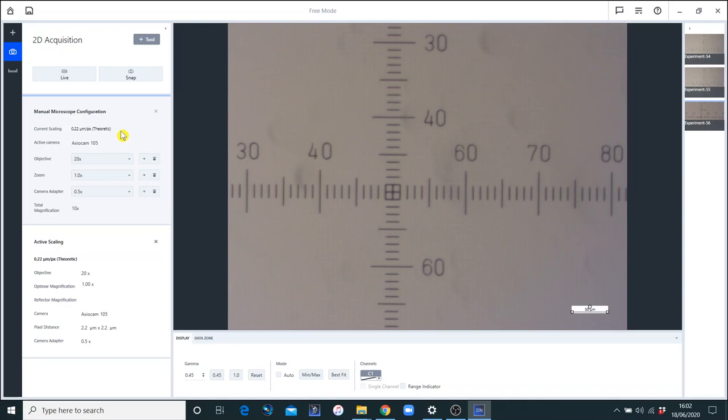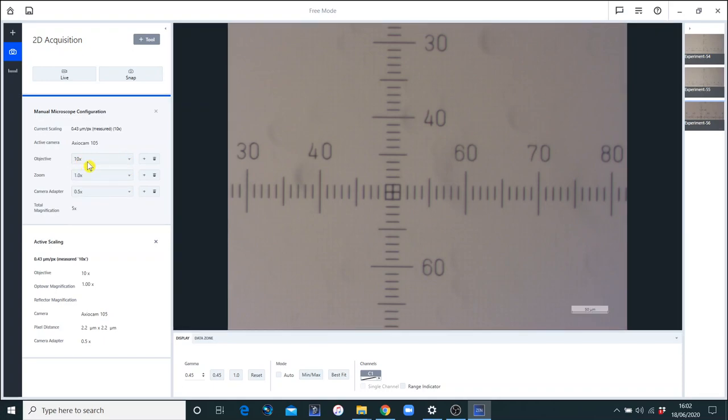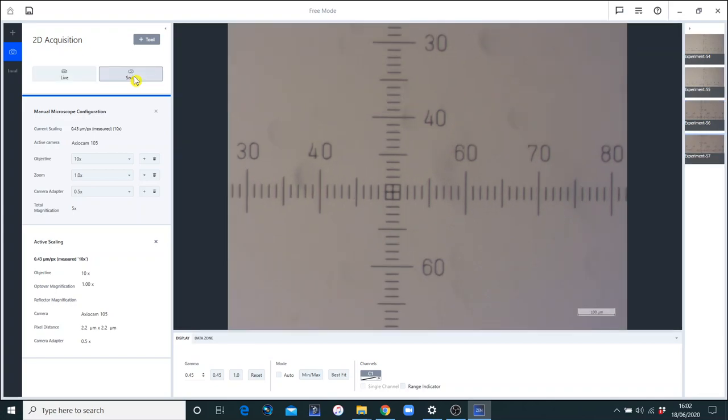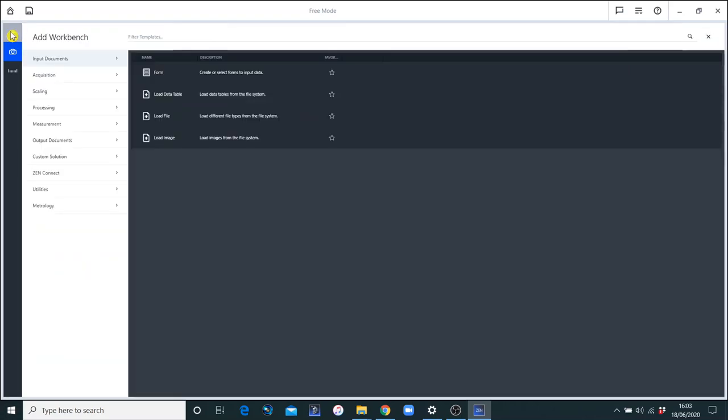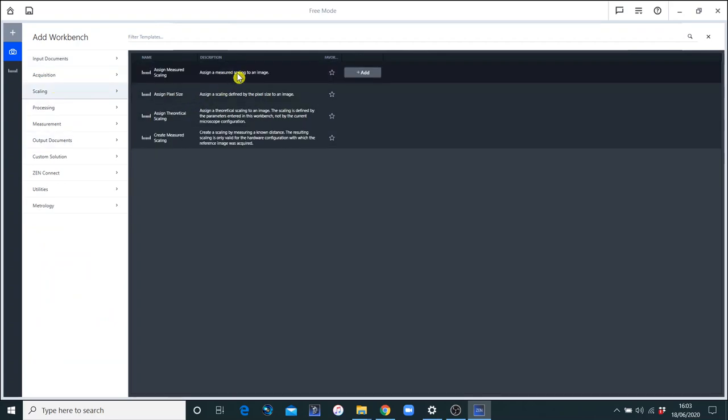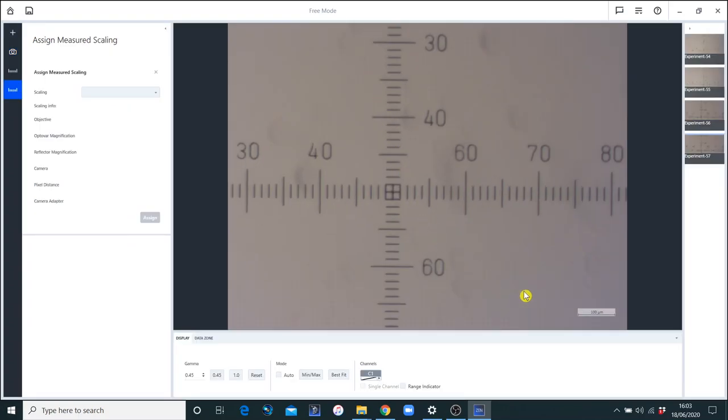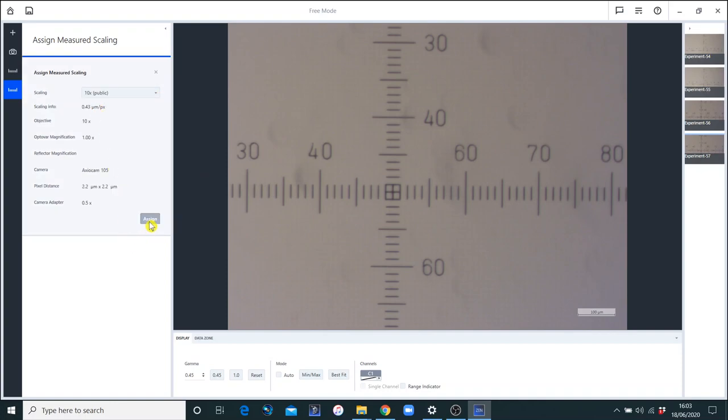So that's how we get a measured scale using a stage micrometer. Now one thing that can happen is if I've got a live image, let's say I have this image here which is live, and I forget to change this, and I have it on a 10 but I'm actually using a 20 image. When I snap this, I've basically created an issue because I've used the wrong scale to collect the image. Now in Zen, that's not a problem really, because I can go back to the workbench and I can add a workbench called assign a measured scale to an image. So this is letting me change the scale when I've collected the picture. So here I would look for the appropriate scaling, click onto that and assign, and then that would correct if I had the wrong scaling.